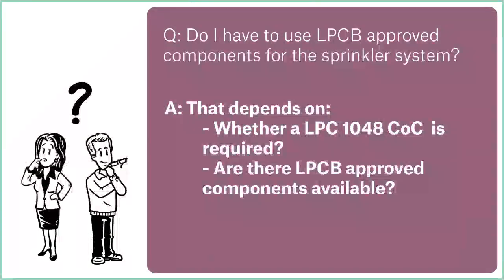Similarly, if you're using residential or domestic code standards, then that kind of approval comes into place as well. So if you are going down the route of LPC approval, then you must be using LPCB approved equipment where available. Okay, so not everything is available. For example, there isn't LPCB approved pipe. Pipe is pipe, as long as it conforms to, let's get this right, is it EN 10255? Which is the standard for pipe thickness and diameter, pipe specifications. So it's obviously very useful for it to conform to that standard. But yeah, there isn't LPCB approved equipment for everything, but where there is, then that should be used.